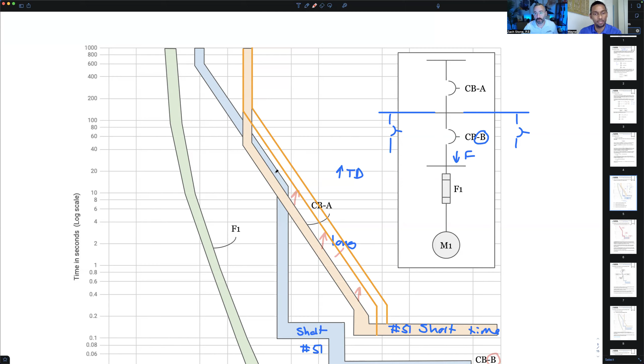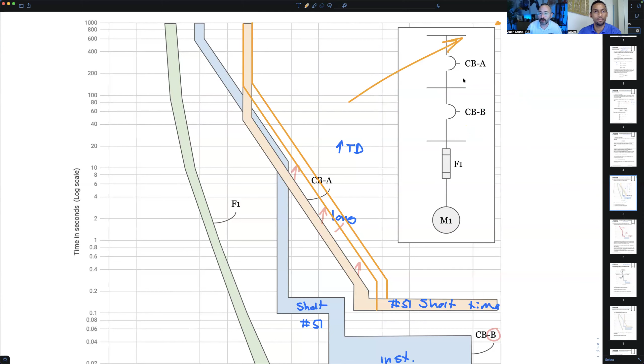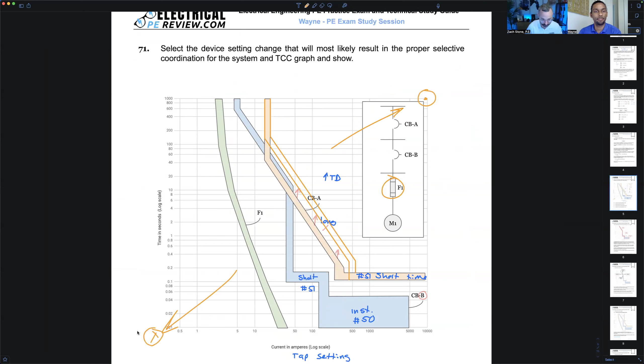So for coordination, you're essentially looking to make sure all your curves are clear of each other. Yeah, exactly, you want them clear of each other. When you look at the single line diagram, you want the most upstream device to be furthest top and to the right—all the way up in this corner—and the furthest downstream device to be down here. You want no overlap from your most upstream device to your most downstream device. That's a really helpful way to look at it.